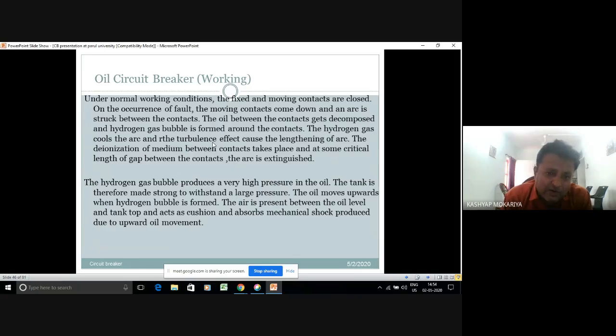The thing which we found here is that the maintenance on an OCB is a bit more. Why? Because once you have decomposition of the oil, or you get carbon particles in the oil, which is known as carbonization in industry, you will have to test that oil. You check the BDV of that oil with the spark gap arrangement and oil testing set. You have to send it to the testing department to get the report. These were part of the routine preventive maintenance of your oil circuit breaker.